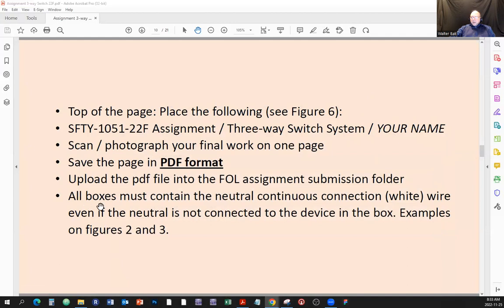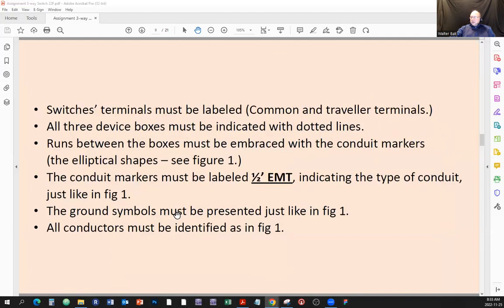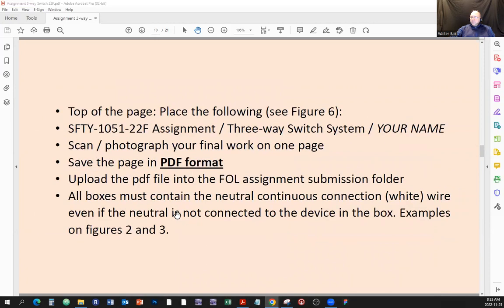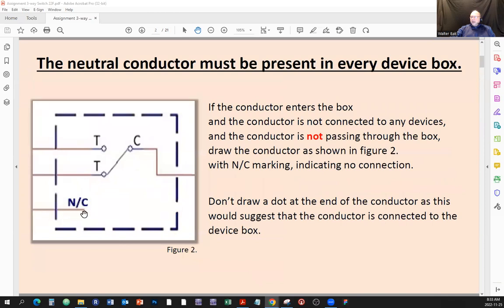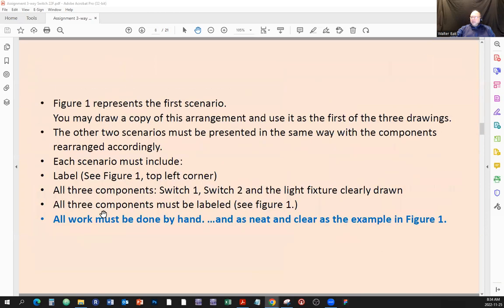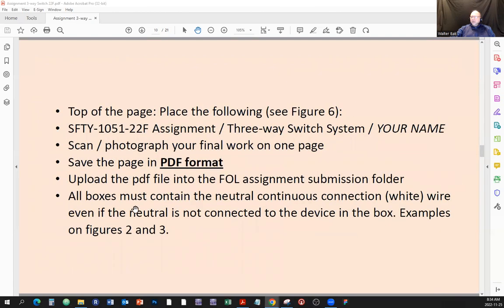All boxes must contain the neutral — the continuous white wire — even if the neutral is not connected to any of the devices. See the examples in figures two and three: here's a neutral passing through the box, here's the neutral going into the box because it has to be there even though it's not connected. This is the rule we have to follow.